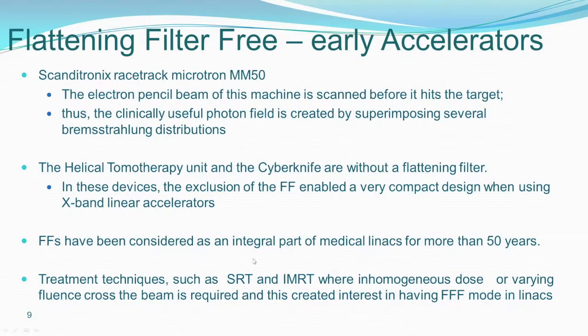So flattening filters have been considered an integral part of the medical linac for 50 years. We couldn't imagine a linear accelerator without a flattening filter in the early days, when we wanted a uniform distribution, a uniform fluence of the beam. But when SRS and IMRT came in, people were looking at inhomogeneous dose distributions and non-uniform fluence across the beam. Then it made sense to ask why make a non-uniform beam into a uniform beam and then again make it non-uniform. Rather, you can use the non-uniform fluence directly, or create some other non-uniform fluence, and use it for radiation therapy. And the FFF mode started becoming part of the linear accelerator.